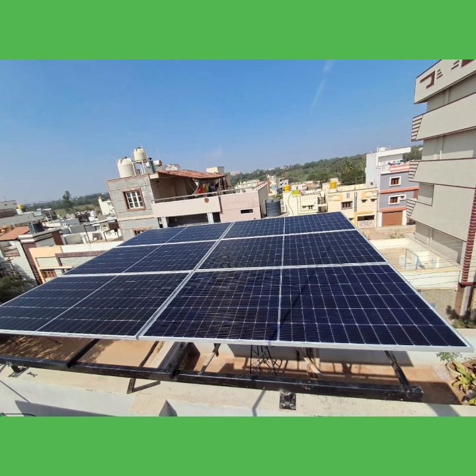To achieve the size of a solar rooftop power plant of say 3 kilowatt, the solar panels can be selected from the suitable sizes. Say 9 numbers of 330 watt peak panels, or 6 numbers of 445 watt peak, or 5 numbers of 540 watt peak. As per ESCOM or EB norms, the solar power plant capacity cannot exceed the sanction load of your home meter. If your monthly meter bill shows 3 kilowatt sanction load, then you can install plant of 3000 watt peak or lower, not even marginally higher than 3000 watt peak.